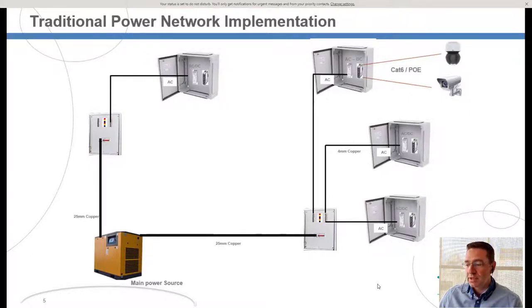From these distribution panels they pulled cables to each single cabinet where we installed our switches. In each cabinet they also installed an AC to DC rectifier to convert the power from AC to DC. So notice how many more elements are used in the traditional design compared to using N1 — all these power-related elements we eliminate completely. No need for any of this.